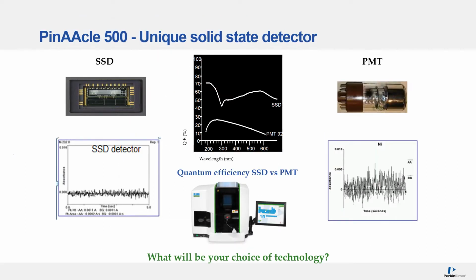As I alluded to on the previous slide, the PinAAcle 500 uses a solid-state detector. Now, the benefit of a solid-state detector compared to the alternative, which is using a photomultiplier tube, marked as PMT in this slide, is that the quantum efficiency of a solid-state detector is far greater across the entire spectrum.